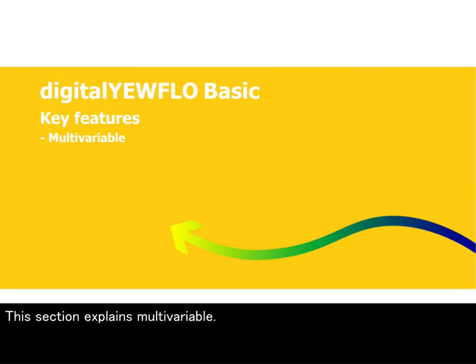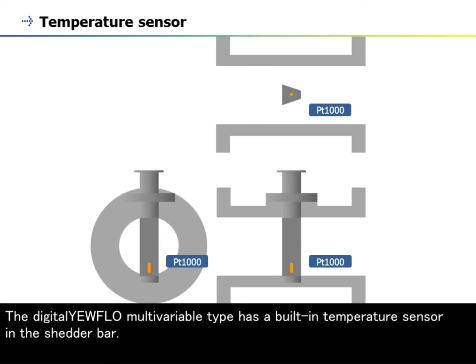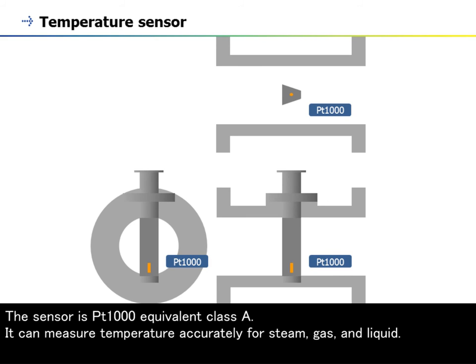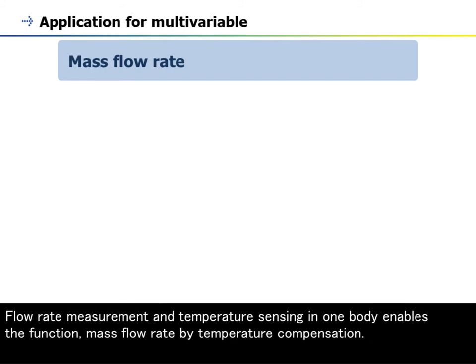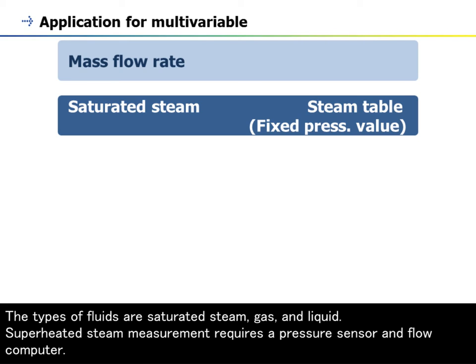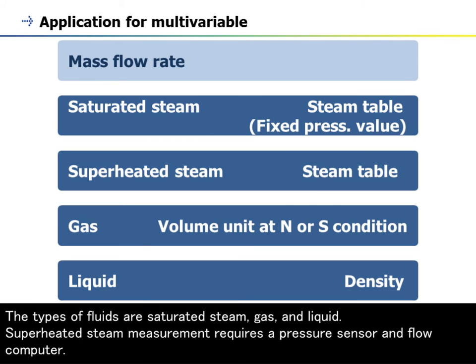This section explains multivariable. The digitalYEWFLO multivariable type has a built-in temperature sensor in the shedder bar. The sensor is PT-1000 equivalent class A. It can measure temperature accurately for steam, gas, and liquid. Flow rate measurement and temperature sensing in one body enables the function of mass flow rate by temperature compensation. The types of fluids are saturated steam, gas, and liquid. Superheated steam measurement requires a pressure sensor and flow computer.